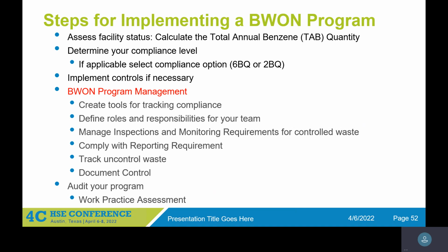Some consent decrees may require you to do monthly, right? That's what I was getting confused with. But you don't have to do Method 21 around the water seals. The unburied sewer lines, that's something that we talked about earlier. You have to do initially and quarterly visual inspections, but no Method 21.